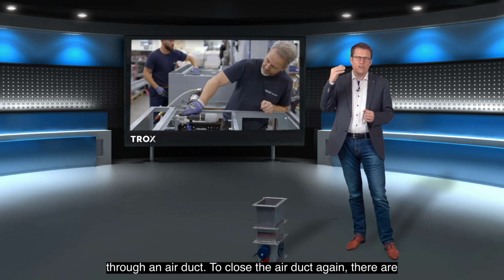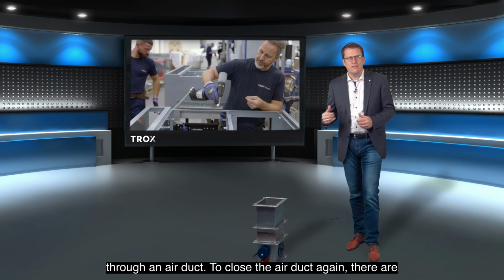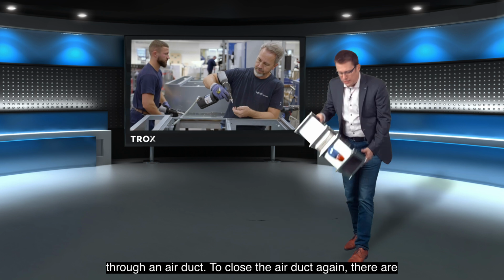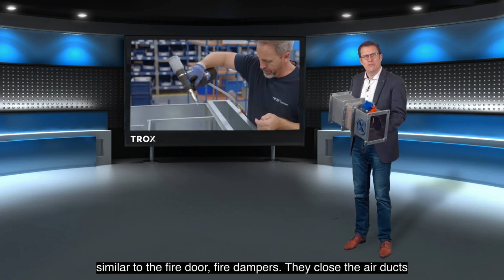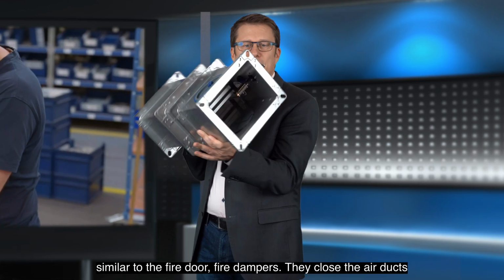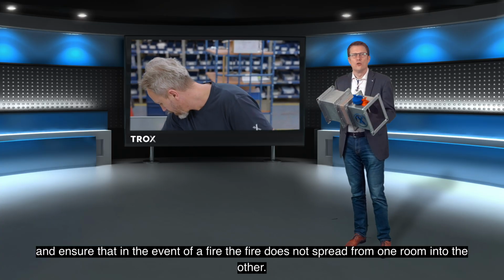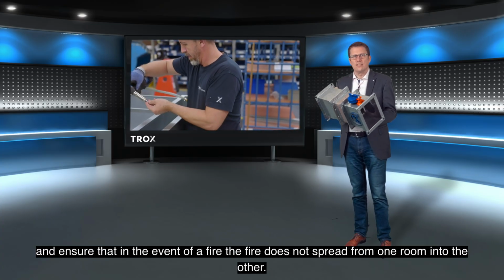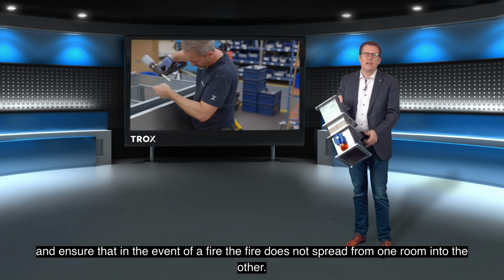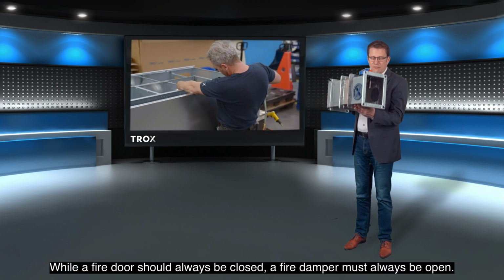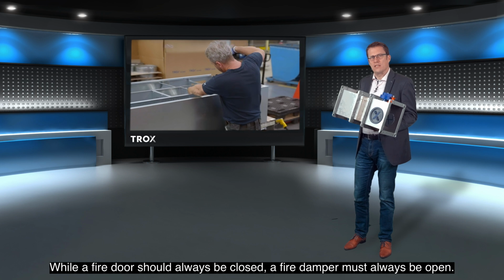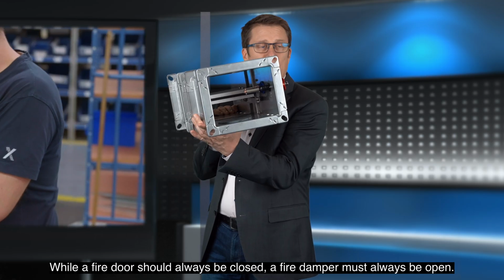The air travels into the room through an air duct. To close the air duct again, there are, similar to the fire door, fire dampers. They close the air ducts and ensure that in the event of a fire, the fire does not spread from one room into the other. While a fire door should always be closed, a fire damper must always be open.